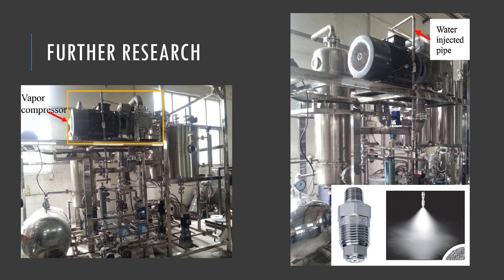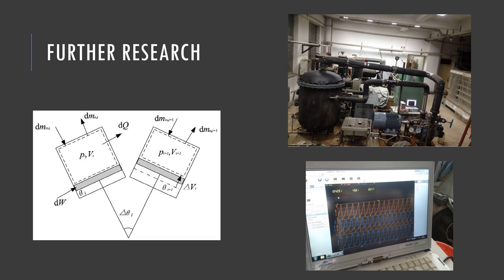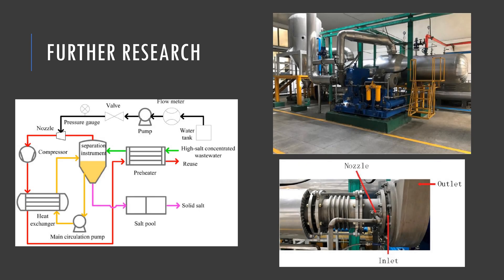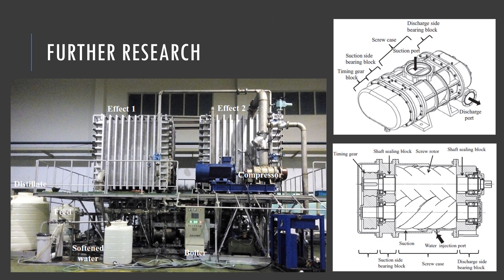Together with our work, significant advancements were made in developing special compressors to handle the requirements of compressing water vapor for desalination and heat pumping applications. One study examined wet compression characteristics of a water-injected single screw compressor in mechanical vapor recompression systems. Another performed both modeling and experimental study of a water-injected twin screw compressor and found significant improvements, especially for high temperature lifts. A further work examined a water-injected centrifugal vapor compressor from theoretical and experimental perspectives, and another developed a water-injected twin screw compressor for a double-effect MVC desalination system, finding notable improvements.